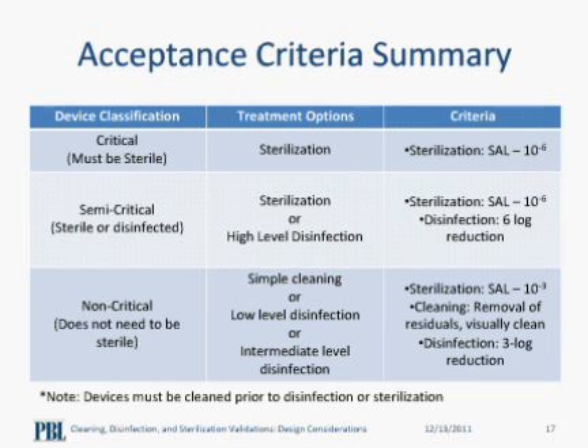Each device classification will have its own acceptance criteria. Critical devices must be sterile with a sterility assurance level of 10 to the minus 6. Semi-critical devices must be sterile with a sterility assurance level of 10 to the minus 6 or disinfected with a 6-log reduction of microbes. Non-critical devices do not need to be sterile and therefore are the most versatile when it comes to reprocessing. The reprocessing can vary from being cleaned, disinfected, or sterilized, and the acceptance criteria is nowhere as stringent as critical or semi-critical devices.